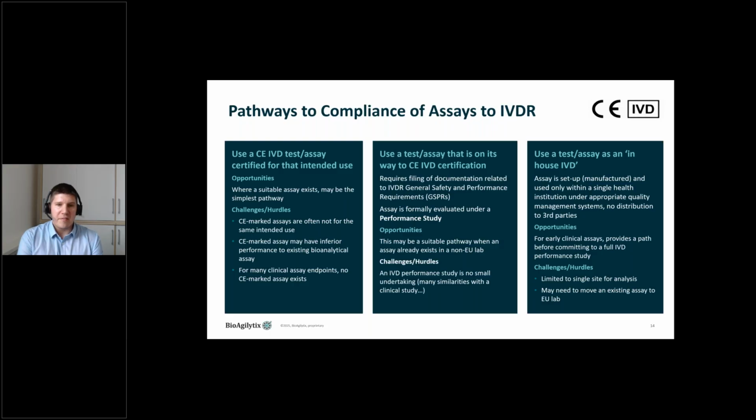So here we have an overview of different pathways, how you can comply to IVDR. The easiest one, if that's available, which is not the case in most of the scenarios we are working with, is the use of an already CE IVD marked test on the market that exactly fulfills the intended use of the study you might be working with. Of course, that would be an opportunity to have easy, direct access to initiate quite quick testing.